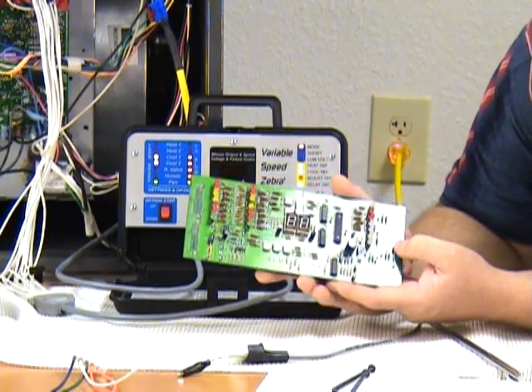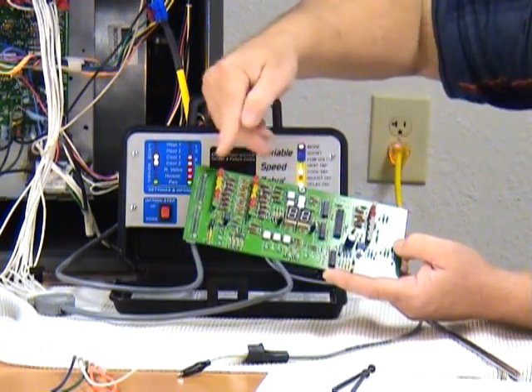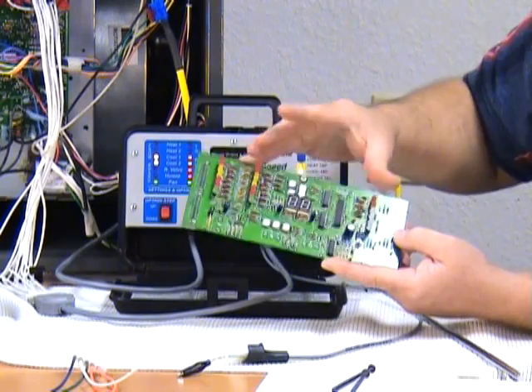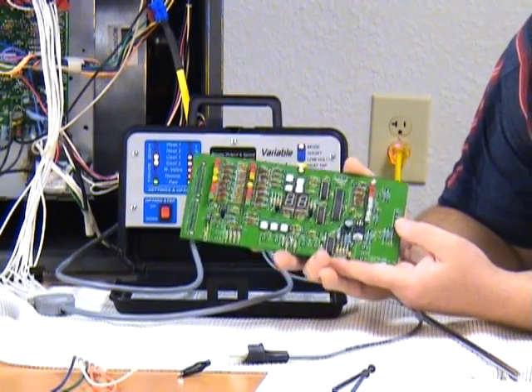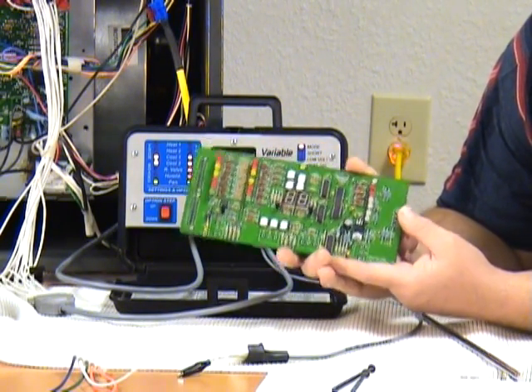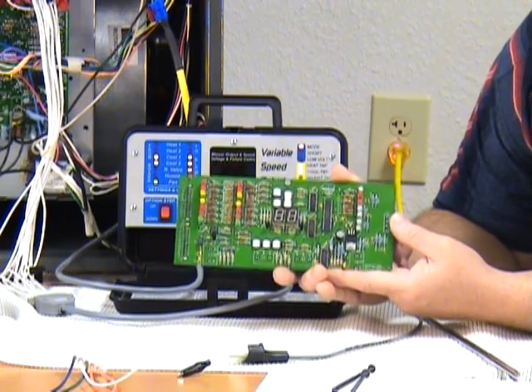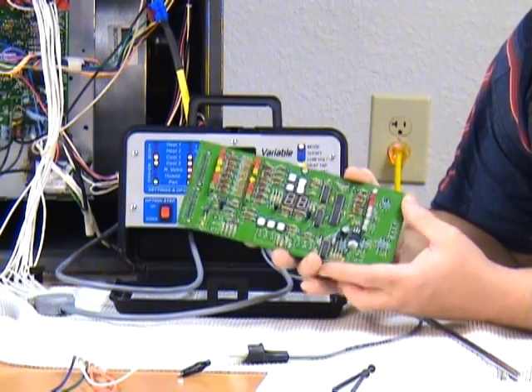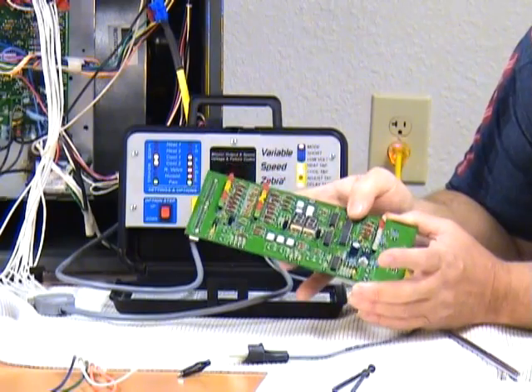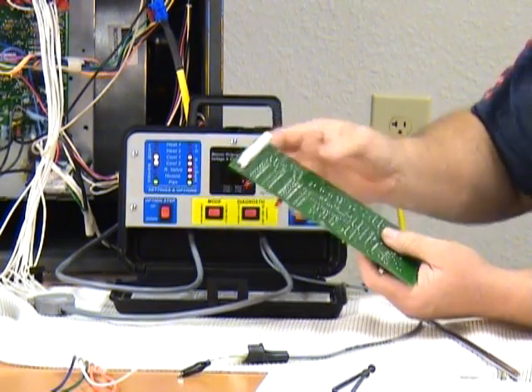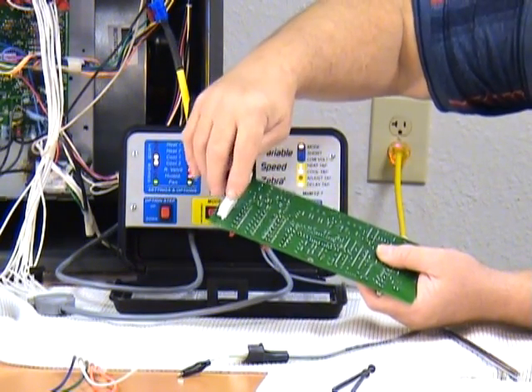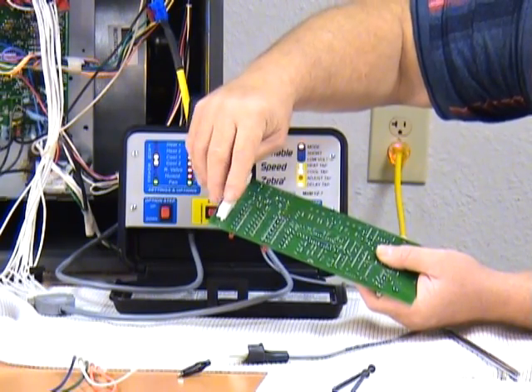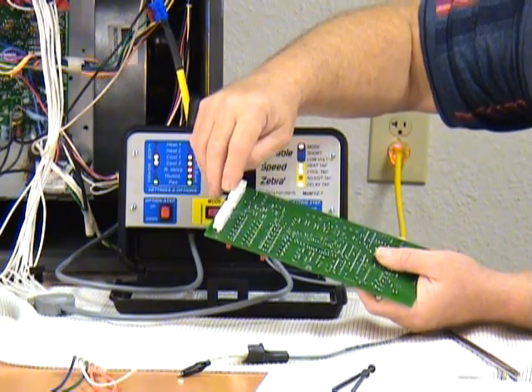Okay, so what you're going to have to do is probably take some compressed air and dry this out. Don't plug in or power up your variable speed zebra. If there's any hint of moisture in there, your warranty will be voided if it blows out the computer parts. They're pretty delicate. The 2 connectors that are on the back of the board are for replacing your wire harnesses should you ever need to do that.